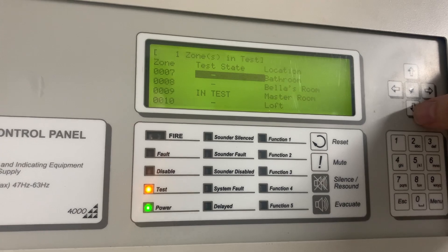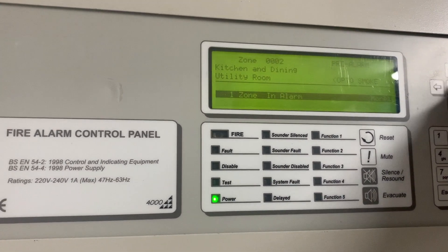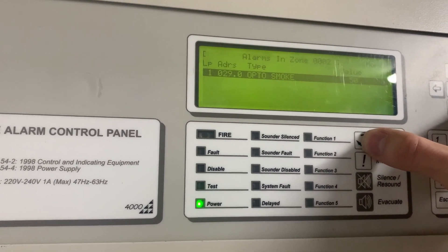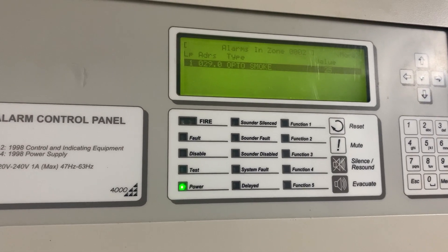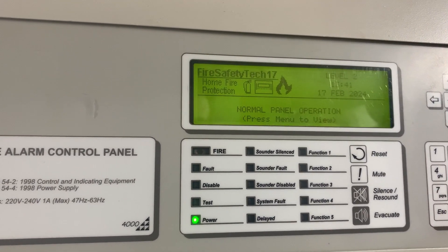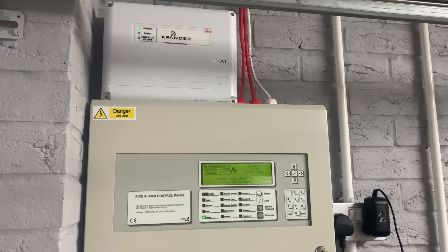The system is back to normal. There was a pre-alarm triggered when coming out of test — I reset it because the value dropped down again. Those Xpander devices don't clear as well, or maybe it's airflow. That concludes the system test for this video. Thank you everyone for watching — I hope you enjoyed the system test and I'll see you in another video. Goodbye everyone.